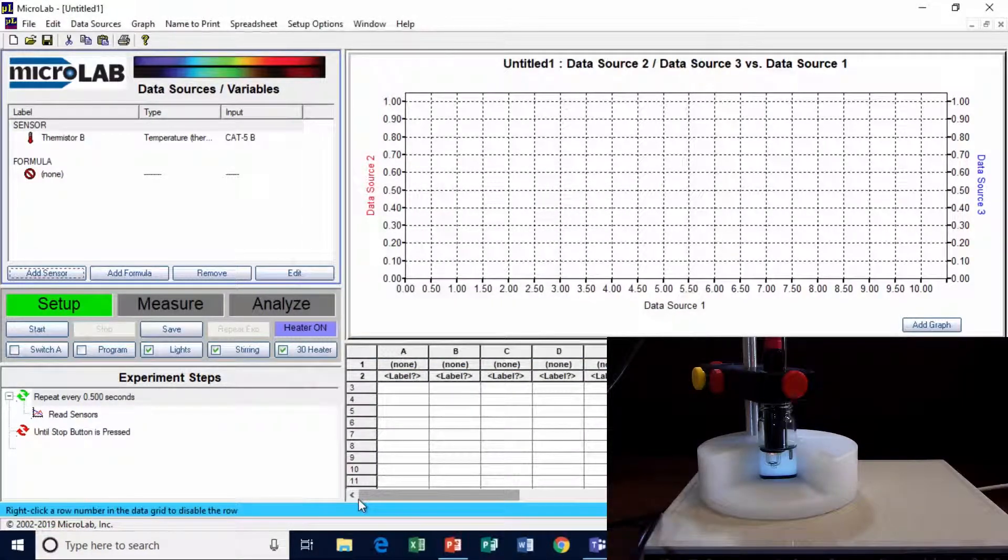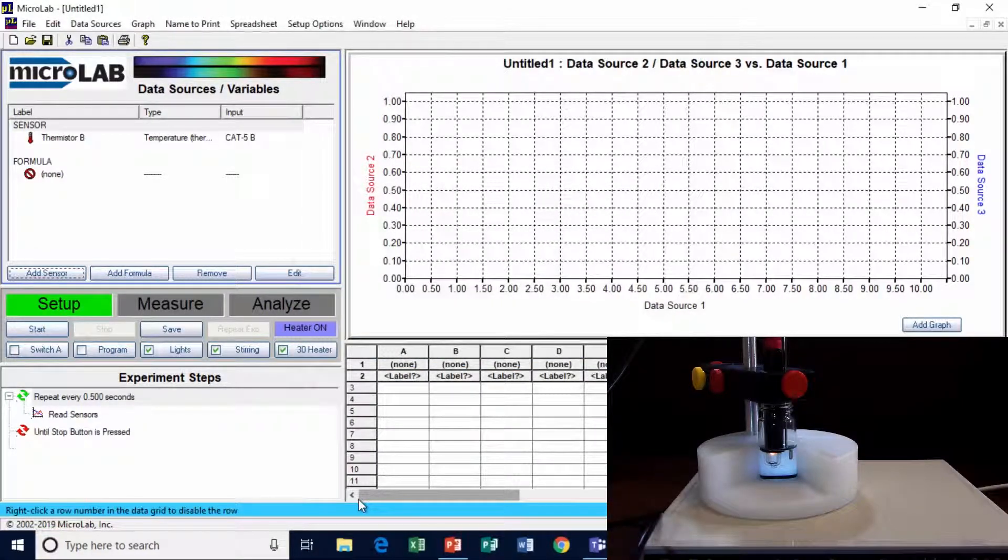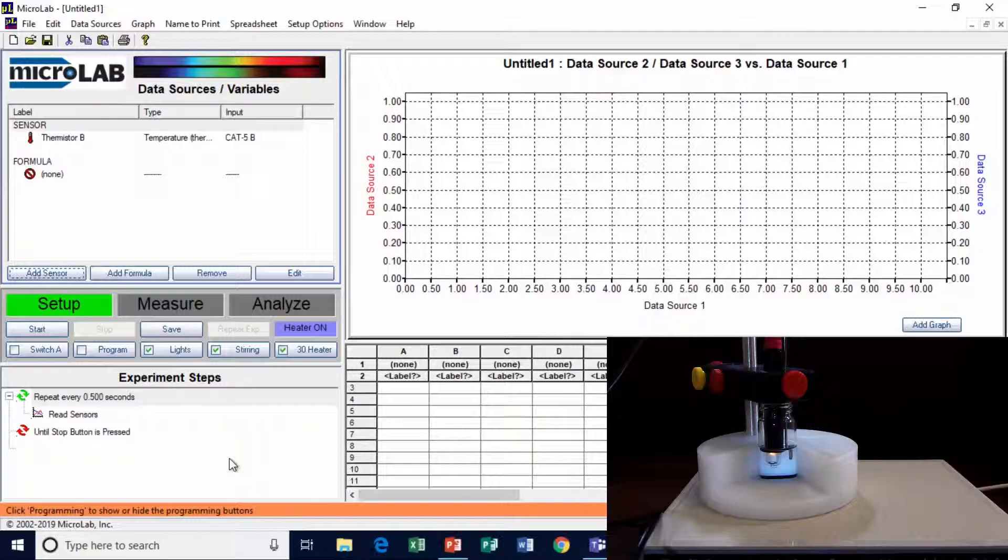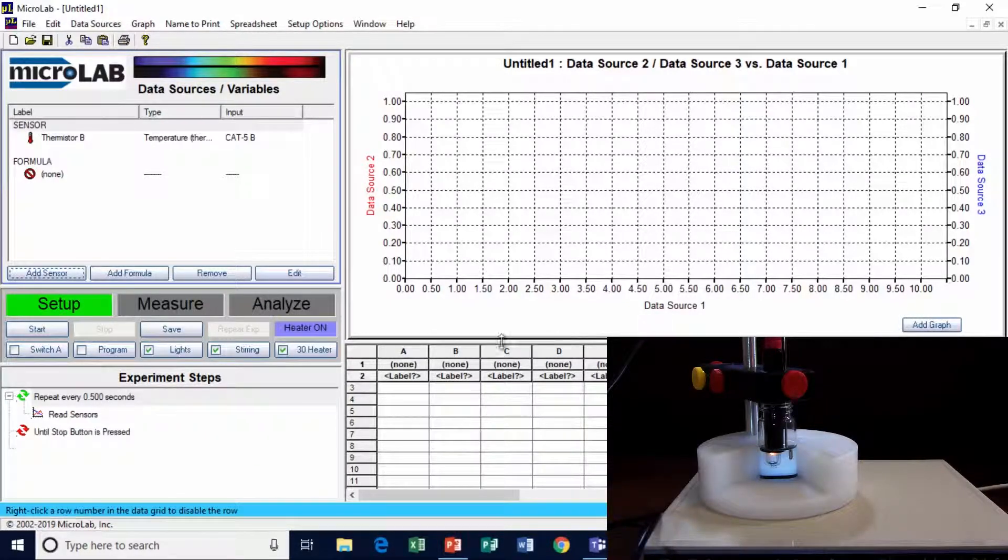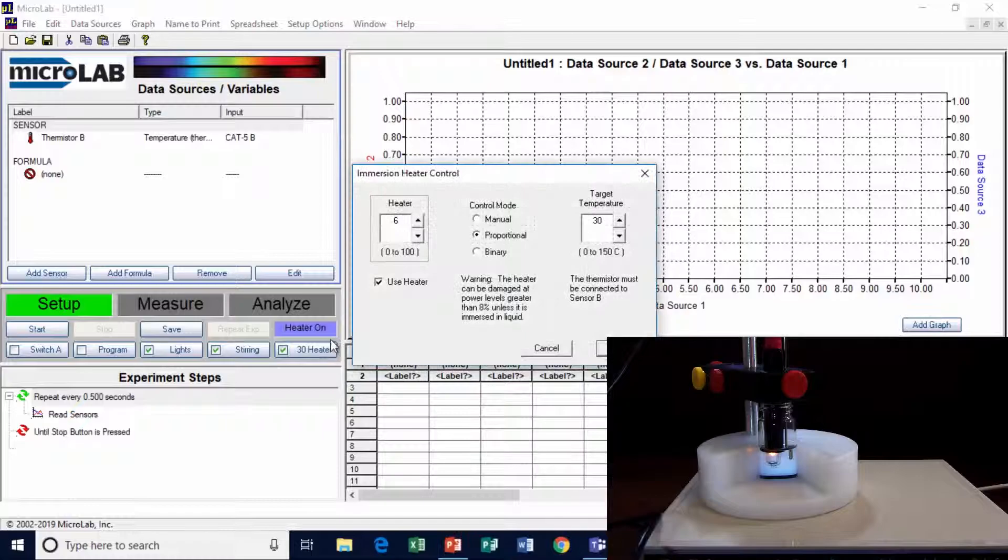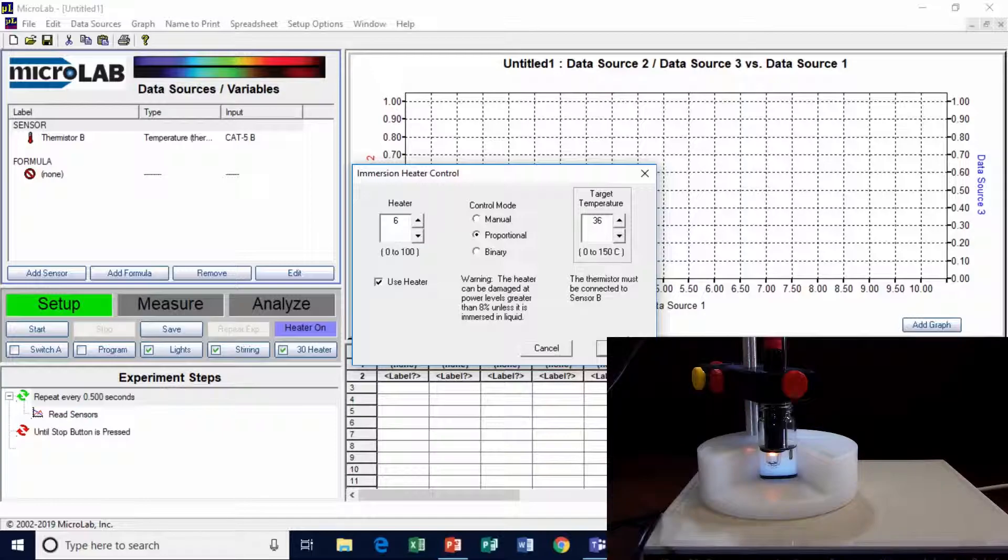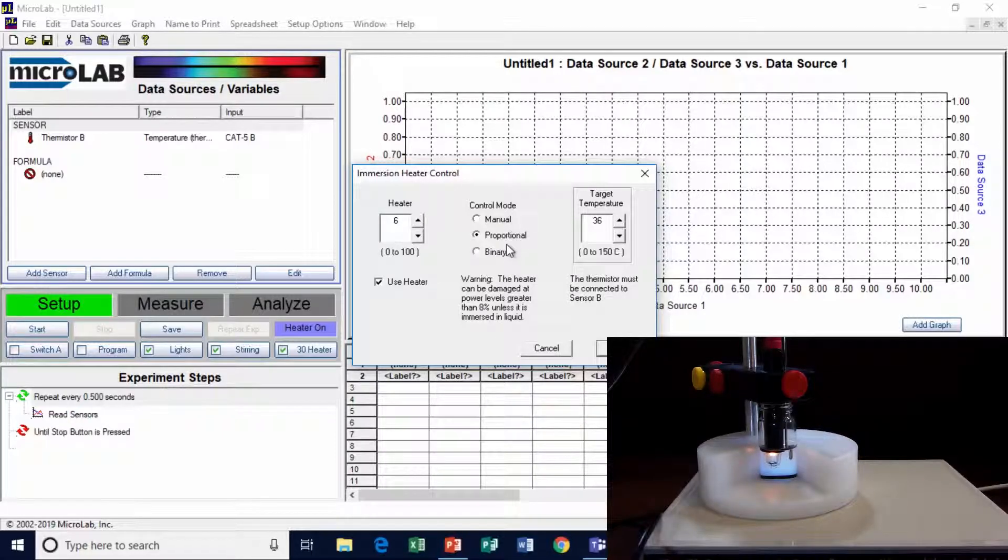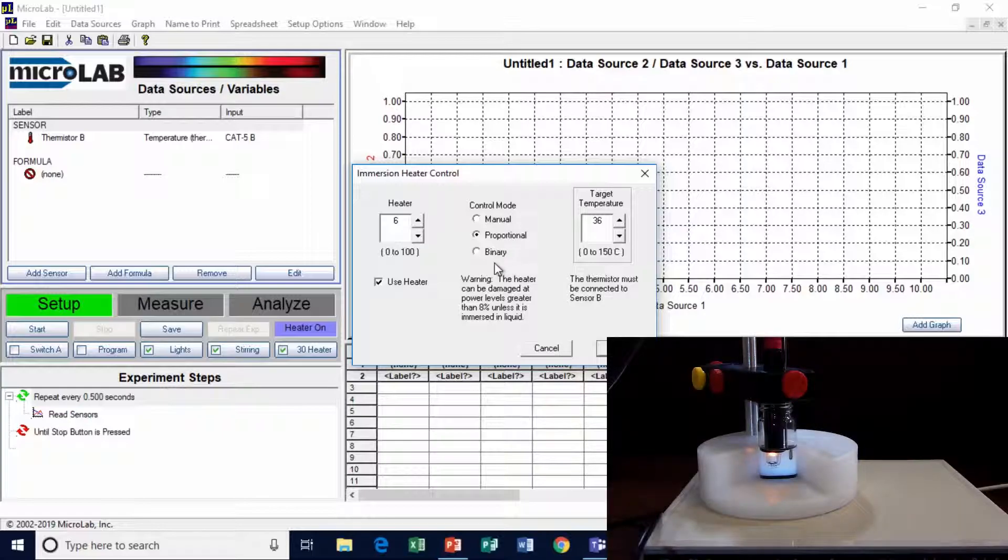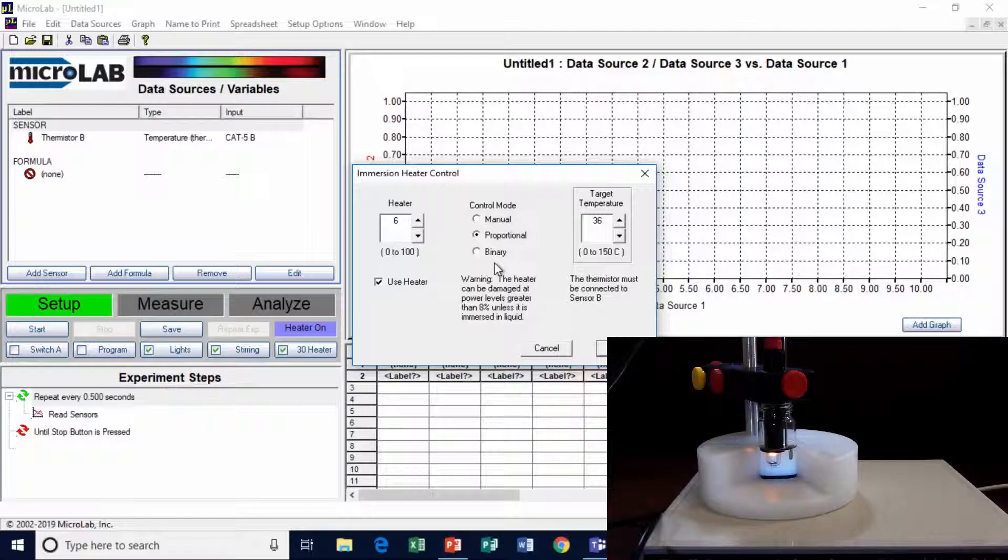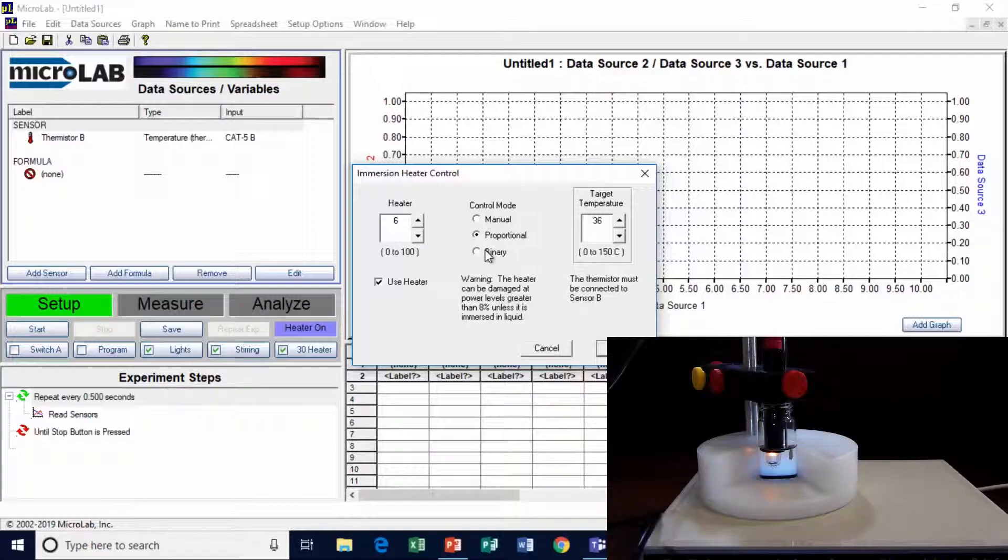It's 28 degrees in that liquid right now, and the heater is on just a little bit. I'm going to turn the heater dialog box on, and let's say I want to run this thing at 36 degrees. So I'll set it at 36. It's got three control modes: proportional, manual, and binary. Binary is on if you're below the target temperature, off if you're above it. Manual, of course, is self-explanatory. And proportional, as you approach the target temperature, the energy applied to the heater goes down. That way you kind of coast right up to where you want.